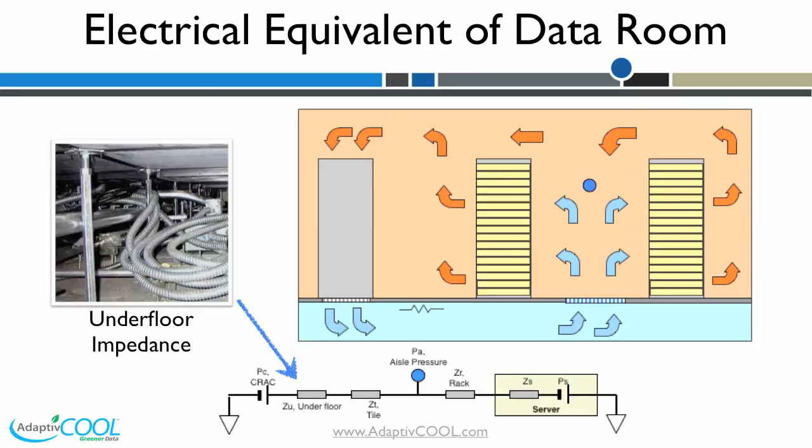If the rack consumes 1000 CFM of air and the tile can only offer 800 CFM, then the rest 200 CFM will be drawn from other areas of the room including the hot aisle. The cold air available at the rack determines the temperature of the server.